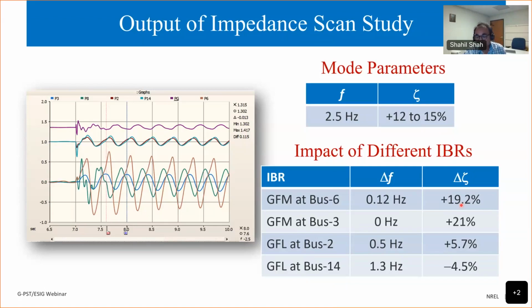The other thing is the grid forming capacity. Here we have seen that these two grid forming inverters are positive contributors of damping. If I remove any of them, it reduces the damping by around 20%, and the damping of this mode is just 12 to 15%. So removing any of these grid forming resources will make this mode unstable. In a way, this gives you a quantity of how much grid forming capacity is required in this system.